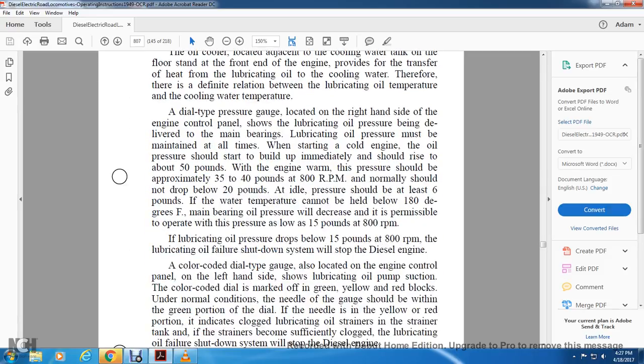The dial pressure gauge located on the right hand side of the engine control panel shows the lubricating oil pressure delivered to the main bearing. Lubricating oil pressure must be maintained at all times. When starting a cold engine, the oil pressure should start to build immediately and rise to about 50 pounds. When the engine warms, the pressure should be approximately 35 to 40 pounds at 800 RPM. Normally it should not drop below 20 pounds. The idle pressure should be at least 6 pounds.